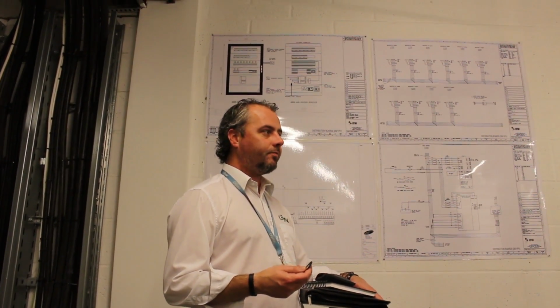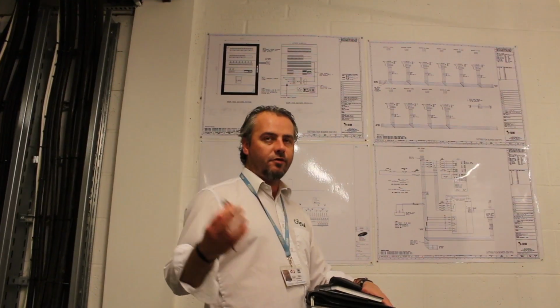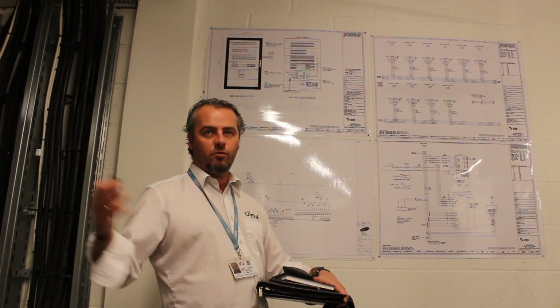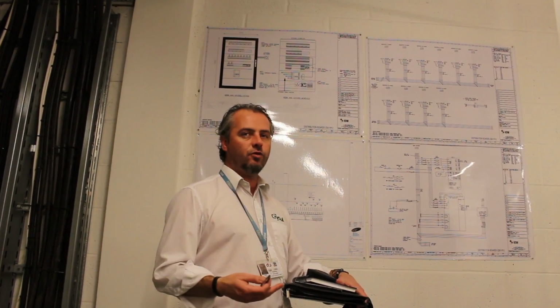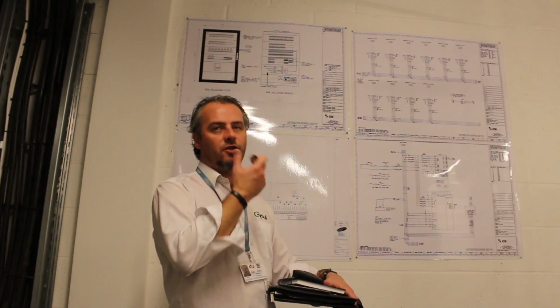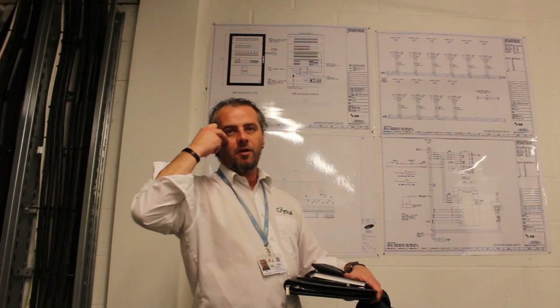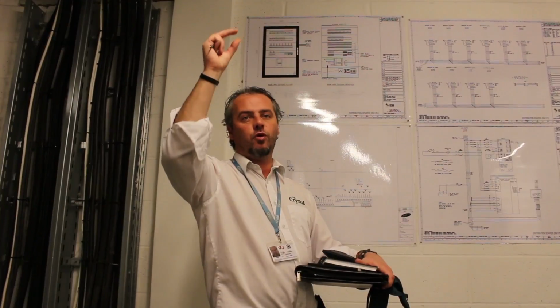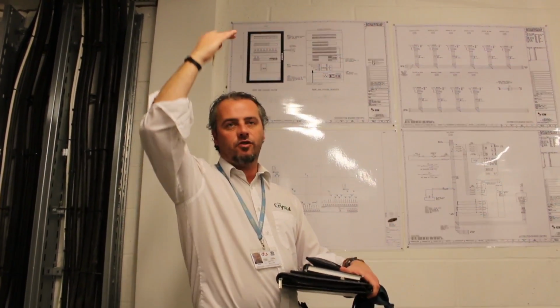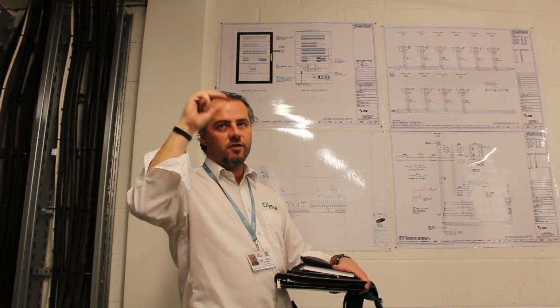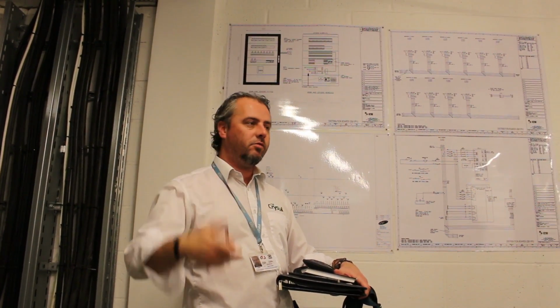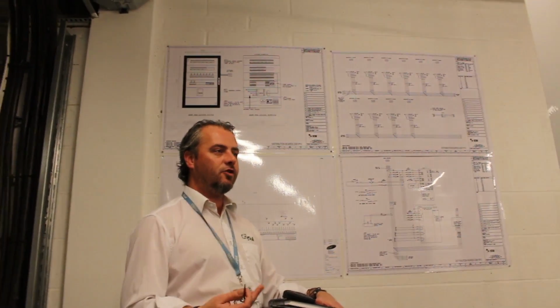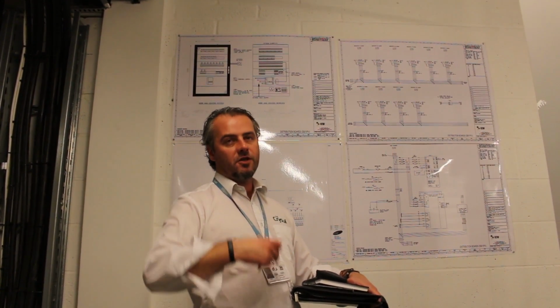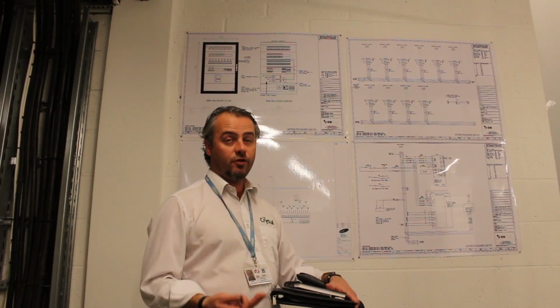So it's interesting that they override it - say we have big conferences with 250 people in one big meeting space, and they feel too warm because the chilling here isn't air conditioned, it's passive chilled beams - literally just cold water pipes above. As the heat rises, you get a natural cooling effect, and you can adjust the temperature of the water flow or the speed. But it's very passive, and some people don't find it effective. It's very good for sustainability and saving energy, but sometimes natural ventilation is needed in addition for some people. So that's kind of how they do the cooling.